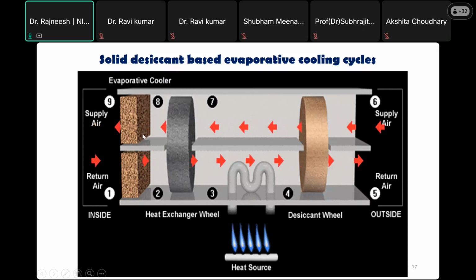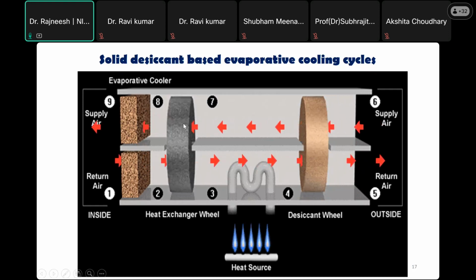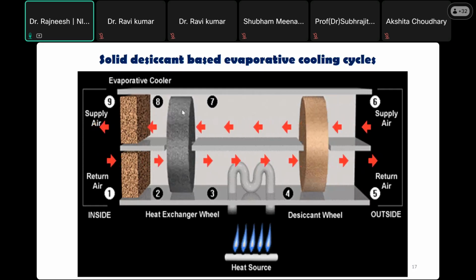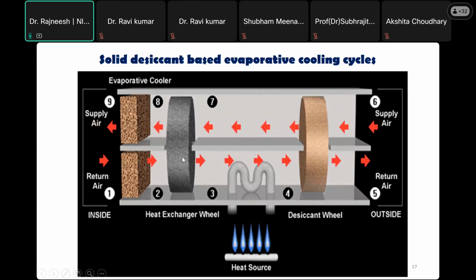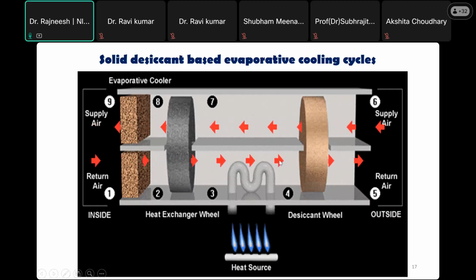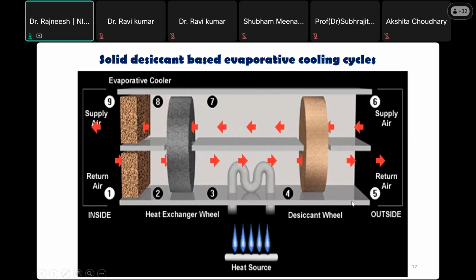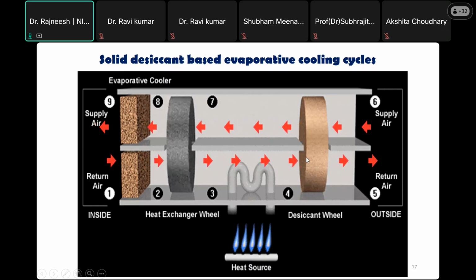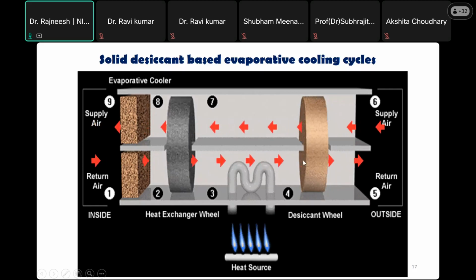Then in the heat exchanger, the thermal energy, that heat, is also increased. That heat will be taken up by again a wheel type of heat exchanger. Then this heat will be utilized in the lower portion to again regenerate the desiccant. The lower portion of the desiccant wheel requires more heat energy to liberate the moisture from the adsorbed desiccant material. So sometimes an additional heater is required to achieve that regeneration temperature.